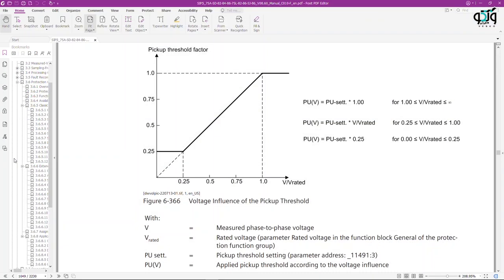In this test, as shown, the characteristic curve is voltage-restrained. In the V over V-rated range between 0.25 and 1, the diagram is linear, where the pickup current value is directly proportional to the voltage increase.